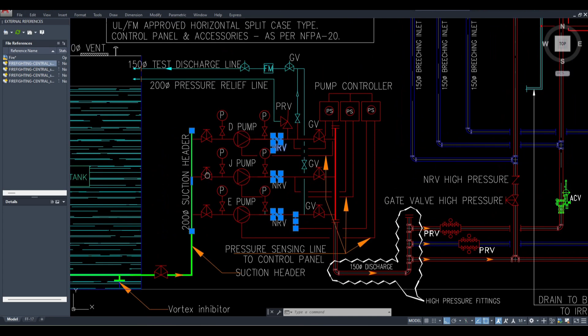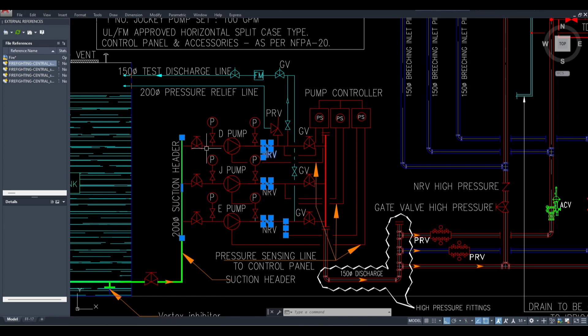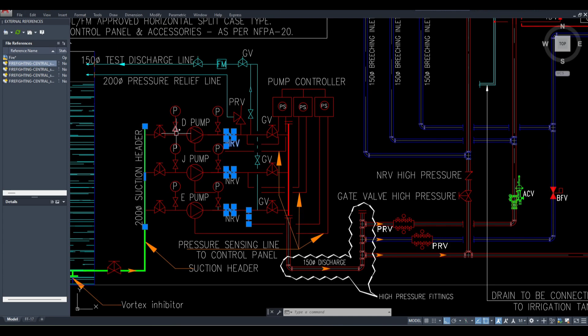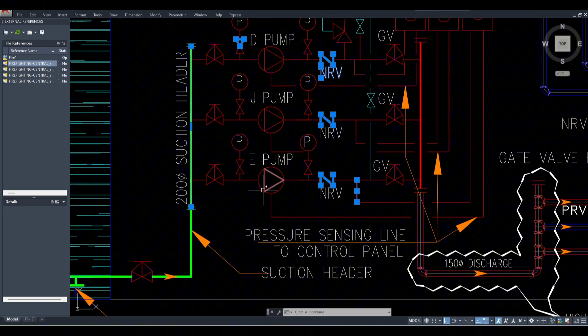Now, so NRV use understood. So very quickly we learned that each system has to be in a parallel connection. Each pump has to be connected, first of all, with the isolation valve. Okay, then the other pipe accessories, like pressure gauges. Okay, then pumps. And whenever pumps are connected, normally the manufacturer recommends connecting with flexible connectors. Okay, but in the fire case, it runs without a flexible connector.